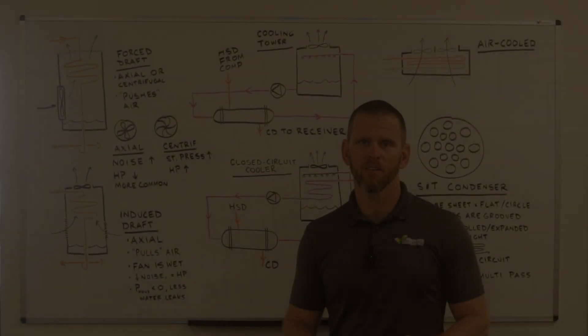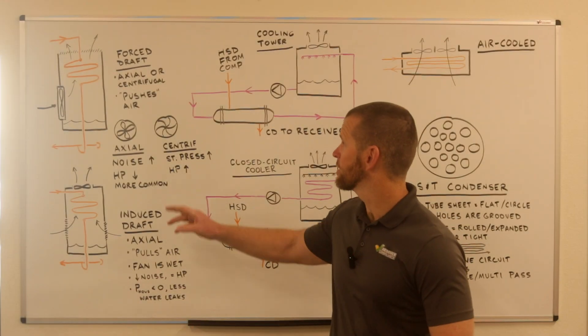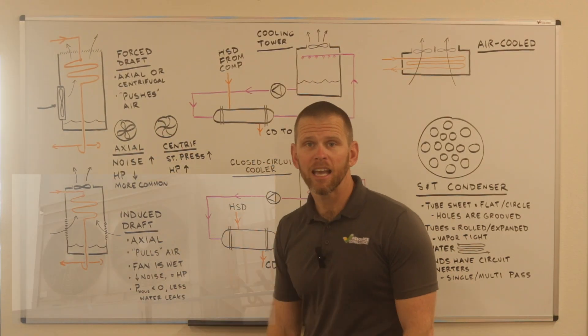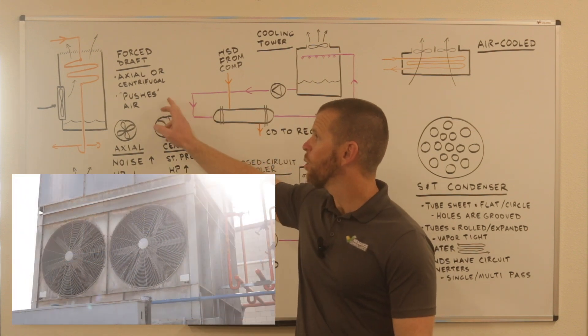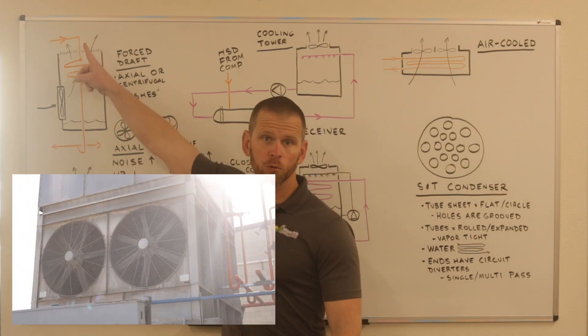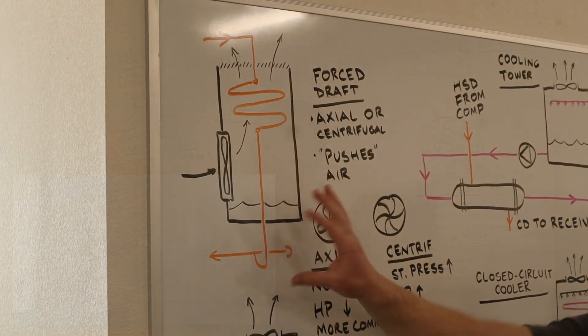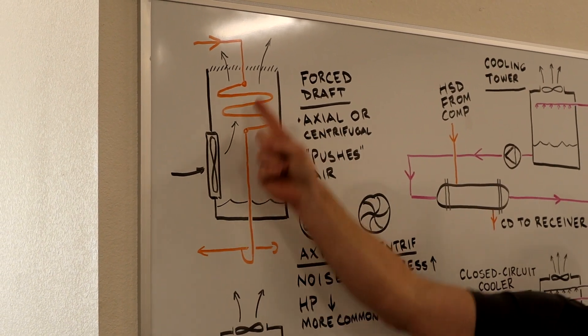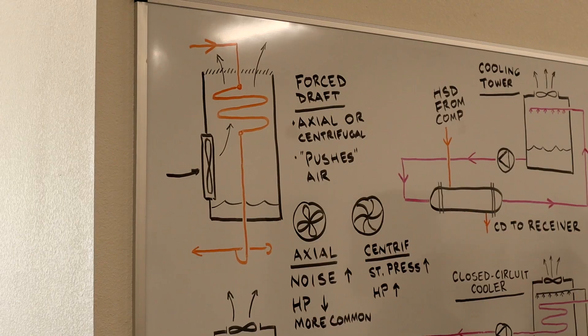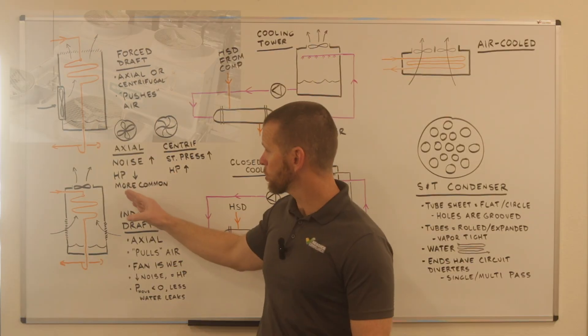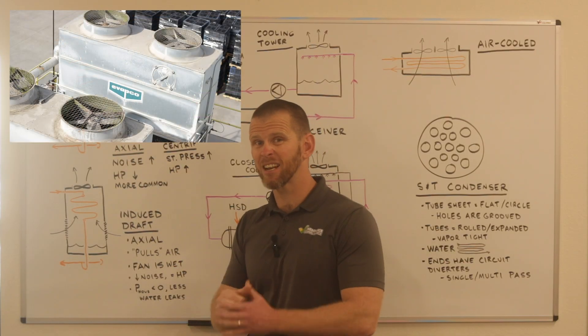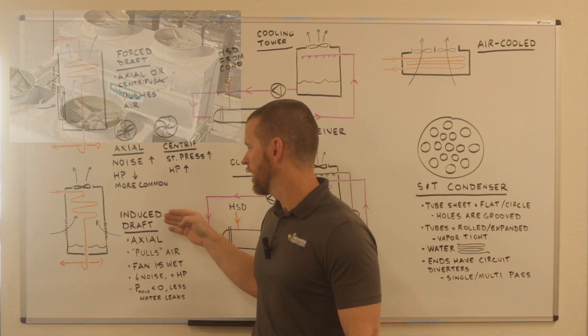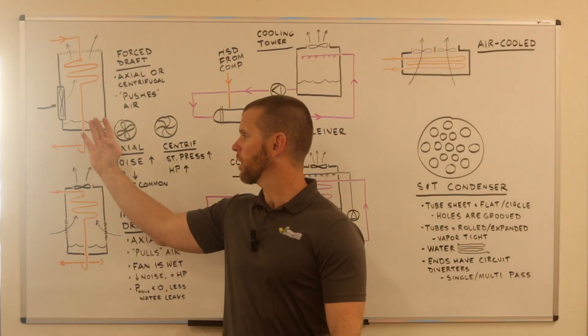One way that evaporative condensers are categorized is by whether they're forced draft or induced draft. In a forced draft condenser, we are pushing air through the coil — the fans are below, pushing air through the coil. Whereas in an induced draft condenser, the fans are at the top and instead of pushing air, it's pulling or drawing the air through the unit, so the air comes in the bottom and is drawn up through the top.